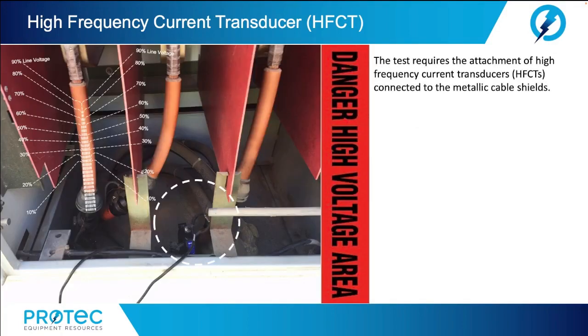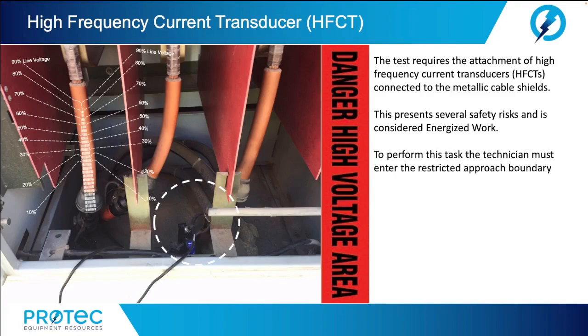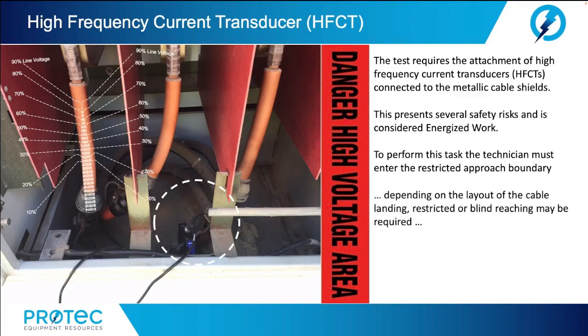Now, a couple items to mention about the use of the high-frequency current transformers. This test requires the attachment of high-frequency CTs to the metallic cable shields. This presents several safety risks and is considered energized work. To perform this task, the technician must enter the restricted approach boundary of the energized service. Depending on the layout of the cable landing, restricted or blind reaching may be required. Now, this is obviously a violation of the NFPA 70E requirements for work involving electrical hazards.